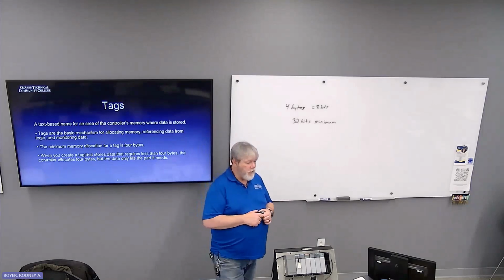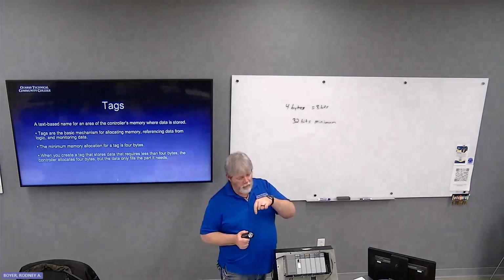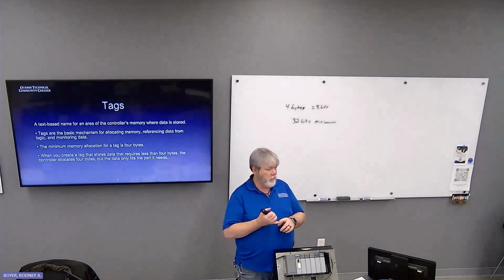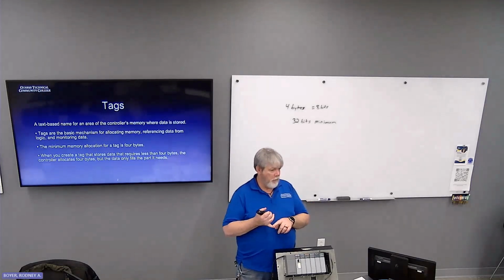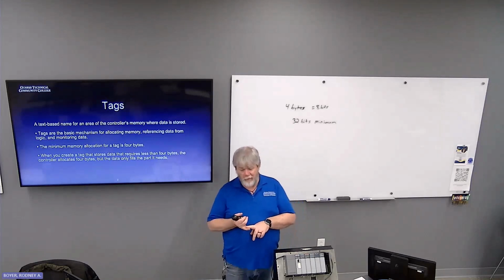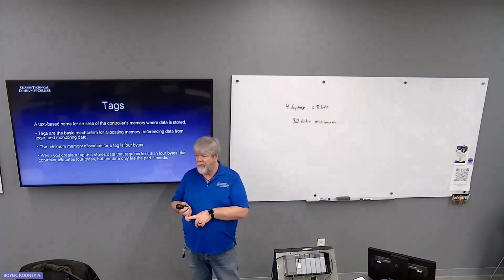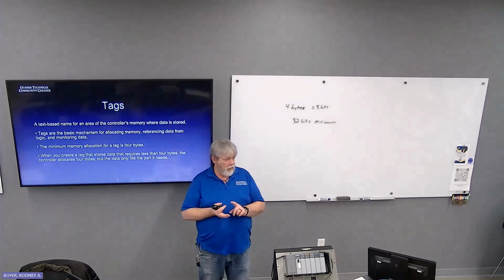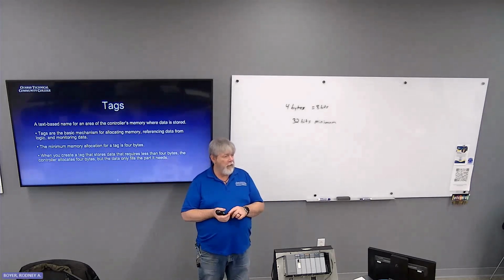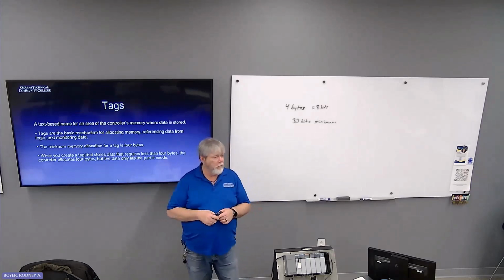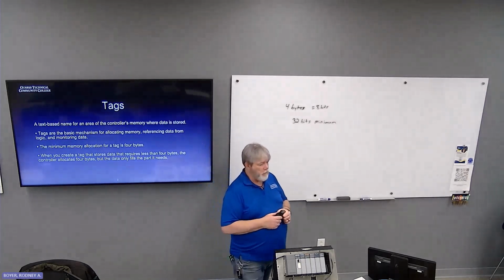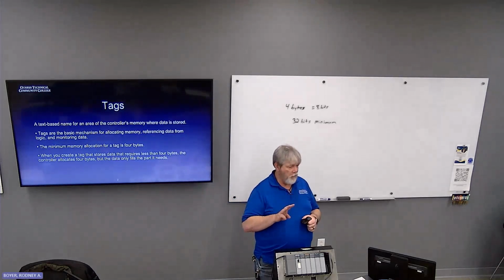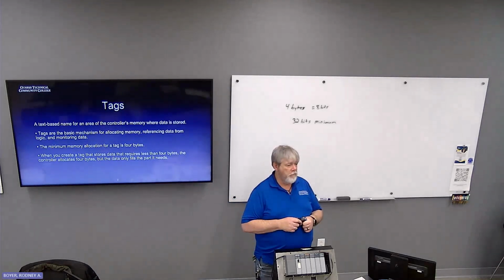So in 32-bit controllers, you have 32 bits allocated for preset, 32 bits for accumulated value, and then a single 32-bit word for enable, timing, done, and so forth. So timers and counters actually use 3 4-byte words.